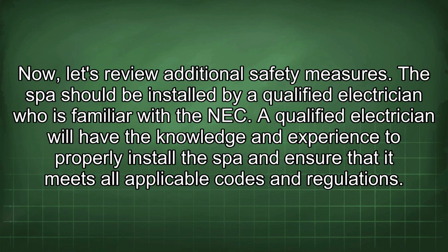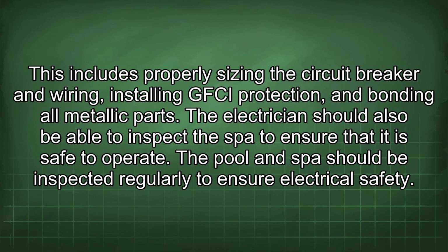Now, let's review additional safety measures. The SPA should be installed by a qualified electrician who is familiar with the NEC. A qualified electrician will have the knowledge and experience to properly install the SPA and ensure that it meets all applicable codes and regulations. This includes properly sizing the circuit breaker and wiring, installing GFCI protection, and bonding all metallic parts. The electrician should also be able to inspect the SPA to ensure that it is safe to operate.